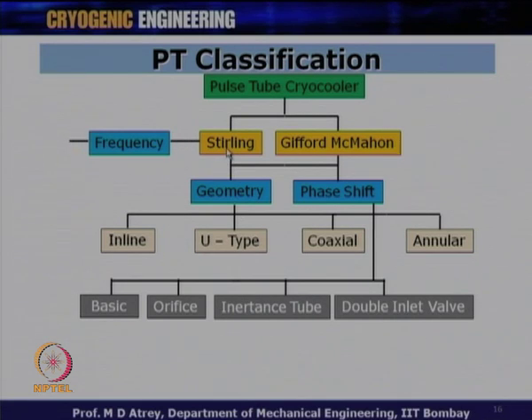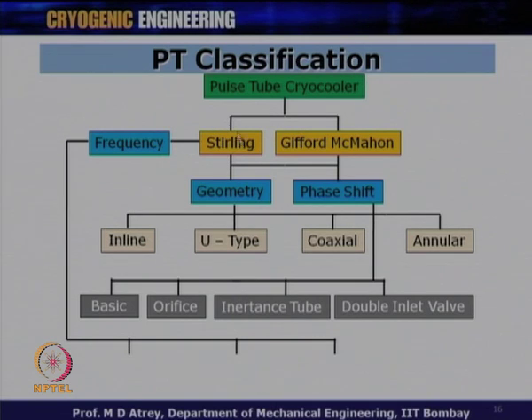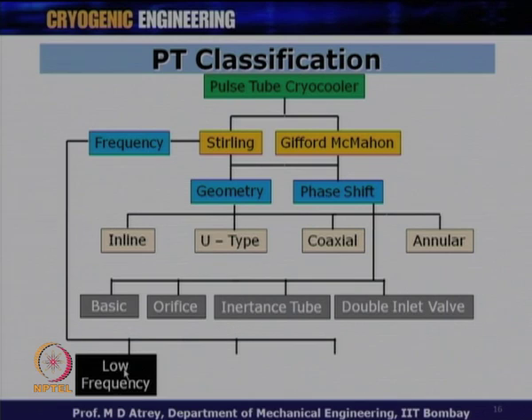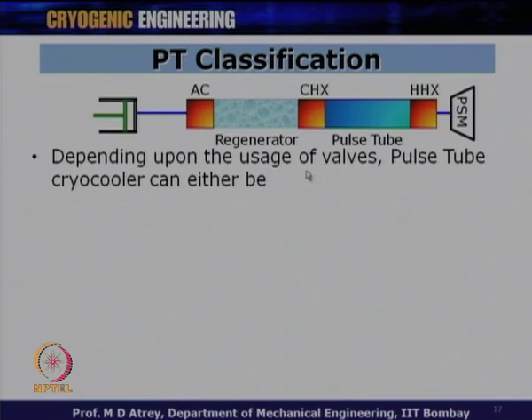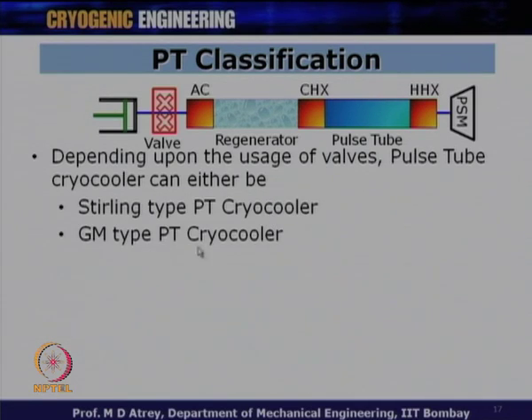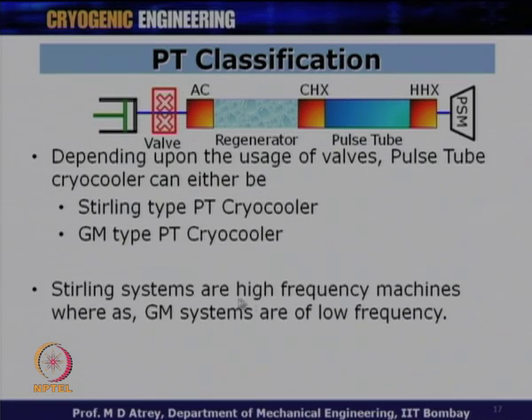Under the Stirling type, based on operating frequency, a Stirling type pulse tube cooler can be classified as: low frequency (less than 30 Hz), high frequency (30 to 80 Hz), and very high frequency (more than 80 Hz). Note that the GM-type pulse tube cooler operates at only 1 to 2 Hz. Stirling systems are high frequency machines, whereas GM systems are low frequency machines.